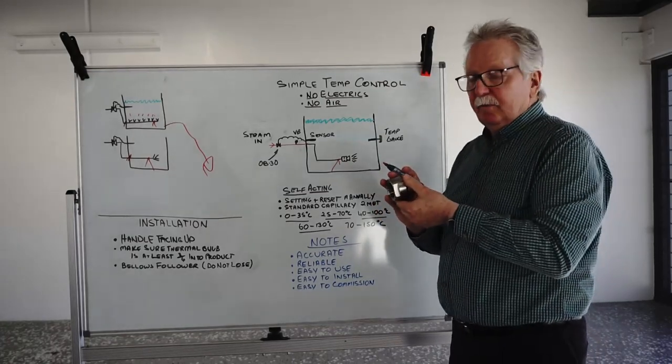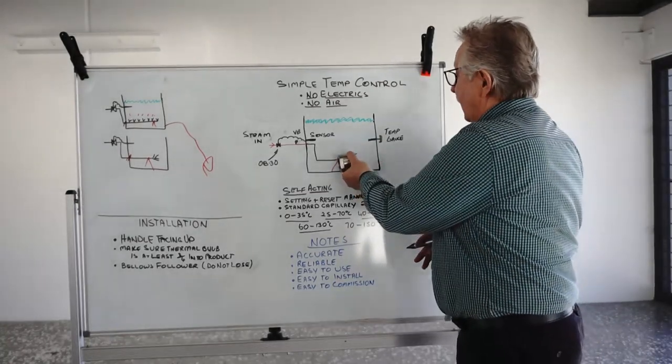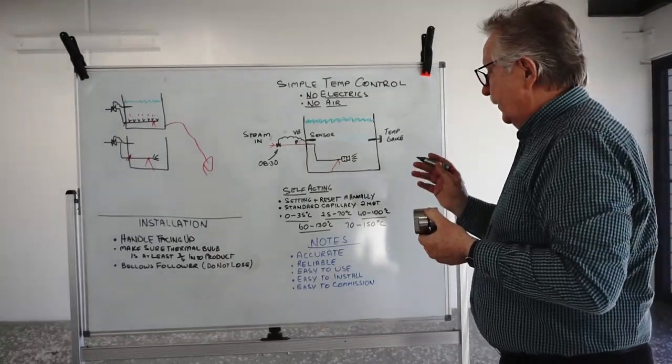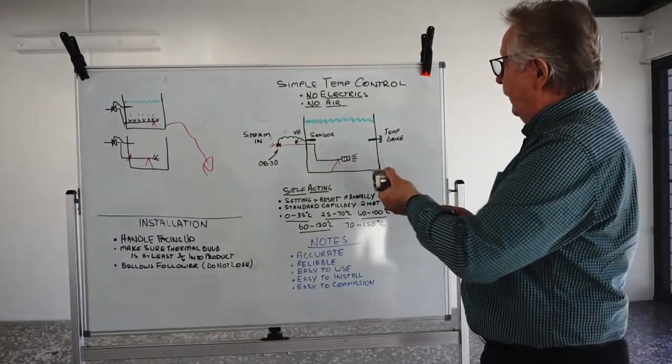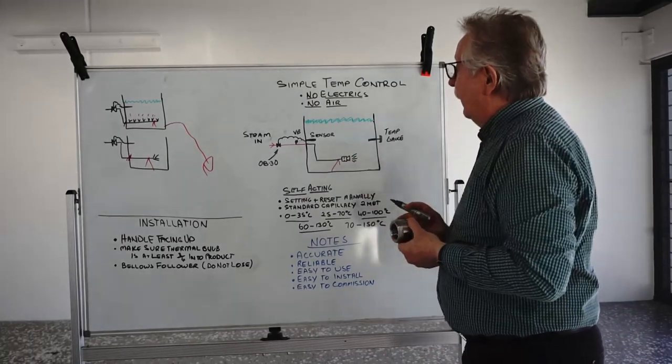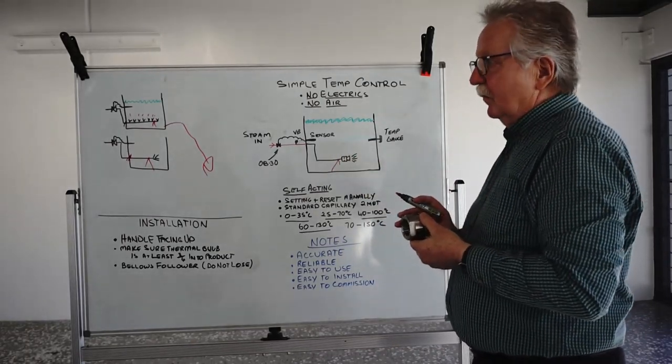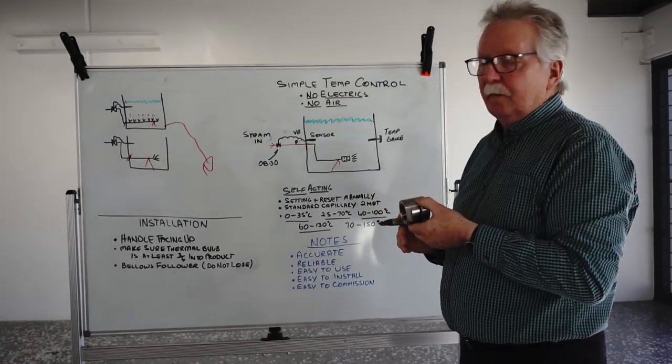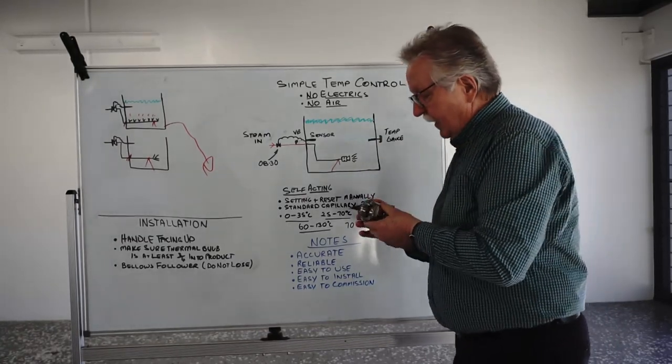They have a maximum operating pressure of 700 kPa, but they do work a lot better at lower pressures. Probably 300, 400 kPa would be better for noise and safety. But they will work successfully up to 700 kPa, no problem.